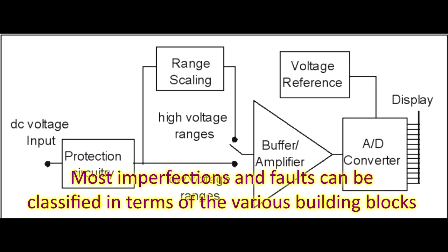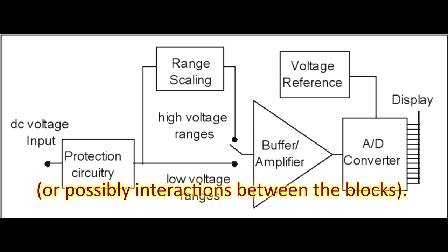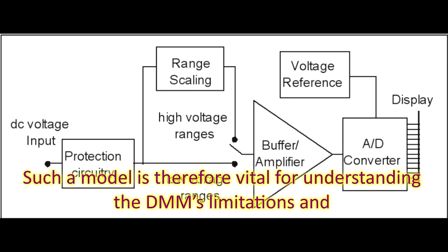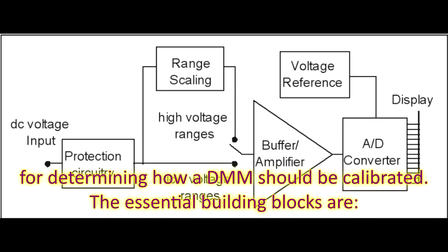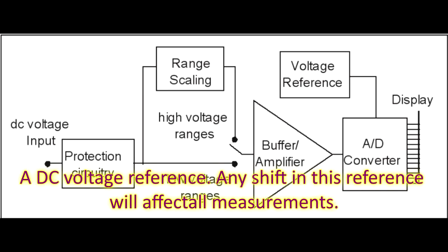Most imperfections and faults can be classified in terms of the various building blocks or possibly interaction between the blocks. Such a model is therefore vital for understanding the DMM limitations and for determining how a DMM should be calibrated. The essential building blocks are a DC voltage reference. Any shift in this reference will affect all measurements.